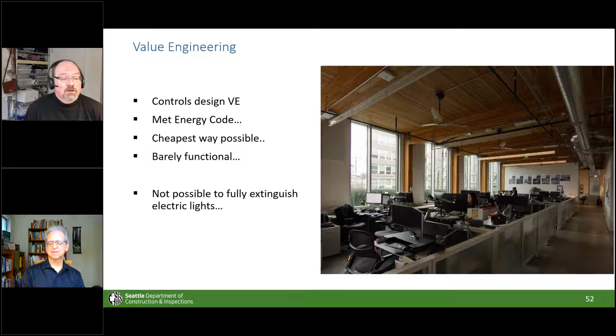So we went ahead and did a lighting controls retrofit using one of these networked lighting control systems, putting in essentially a load controller per light fixture. They're not LLLC fixtures, since as Duane alluded to earlier, some fixtures it's literally not physically possible to attach a sensor to — these are one of those. But we did get individual light fixture control, so every fixture is individually addressable, and then we added all of the high-end controls.